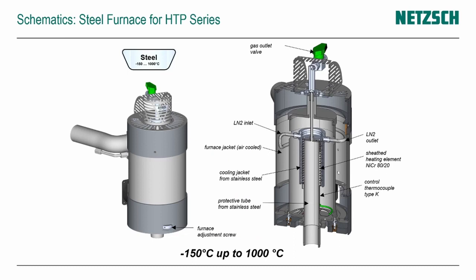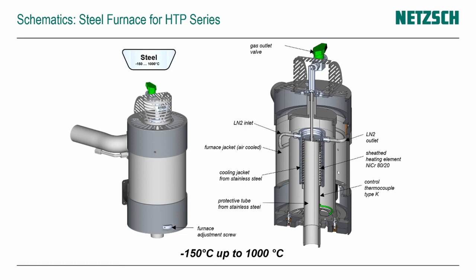Experienced users may note that the STA has different furnace options, including a coolable steel furnace with a range of −150°C to 1000°C — seemingly the perfect solution for a combined TGA-DSC approach in the low temperature range, allowing measurement of polymer phase transitions in the sub-ambient range and standard TGA analysis up to 1000°C. However, one remark: the steel furnace has a protective tube made of steel with an inert coating, which withstands reactive atmospheres, but it is not completely comparable to a ceramic protective tube.